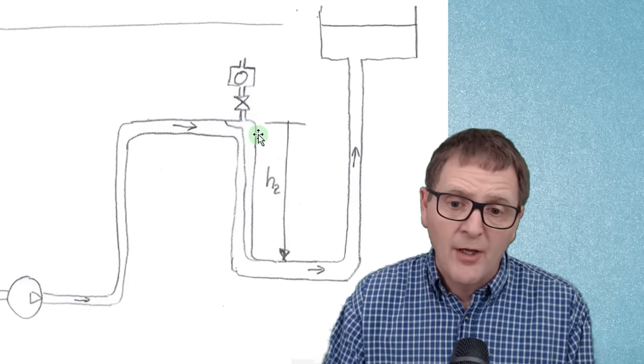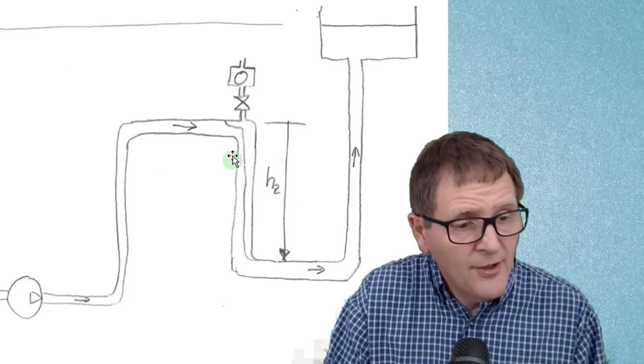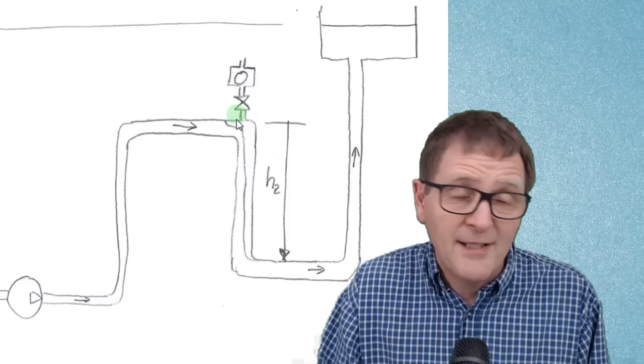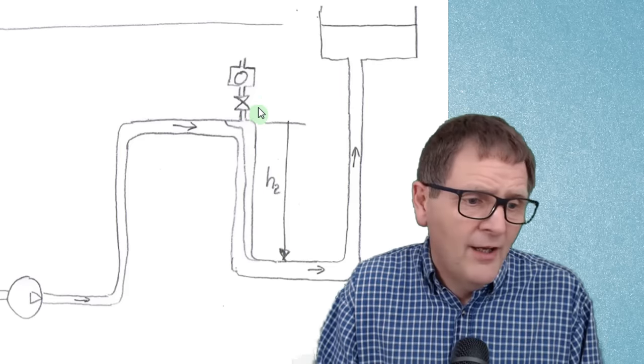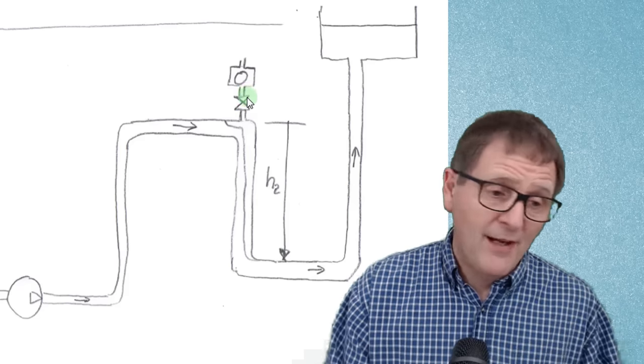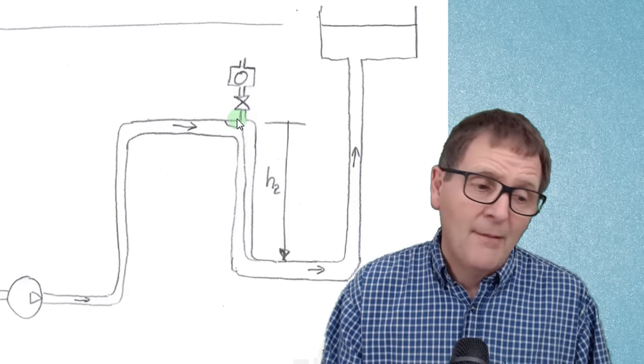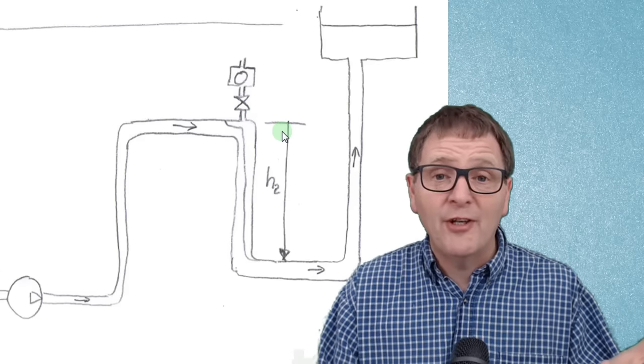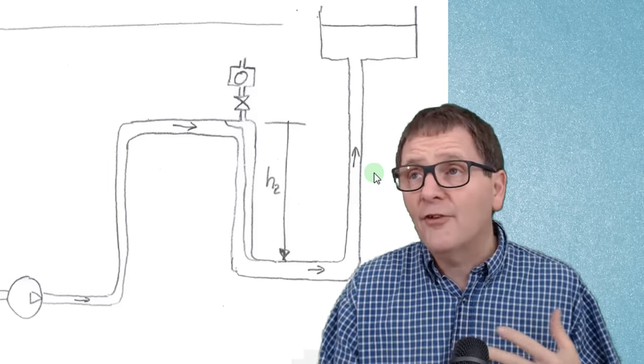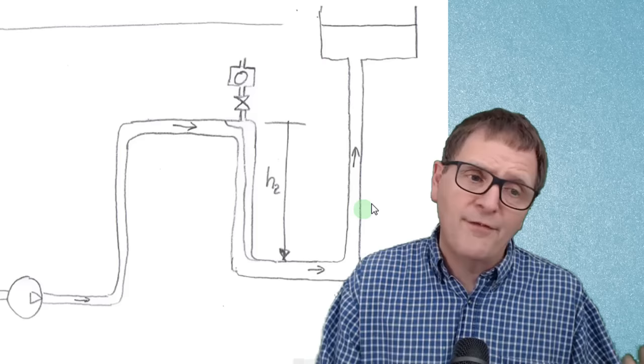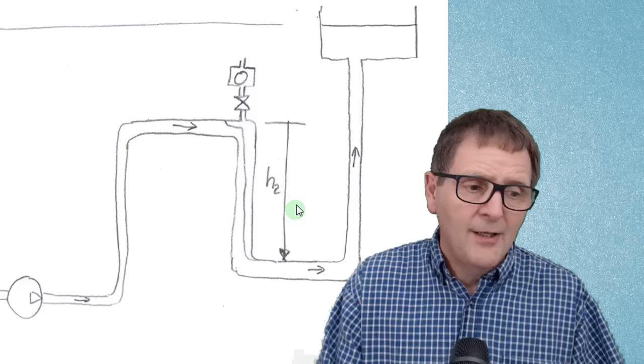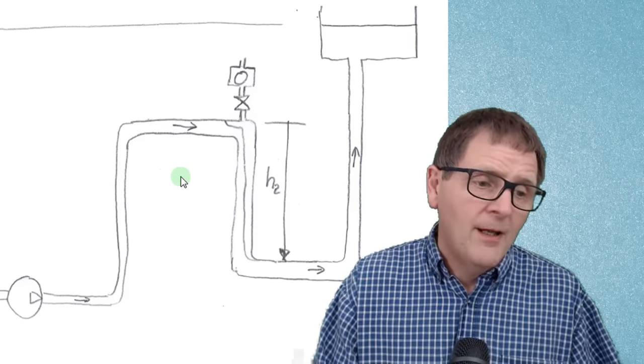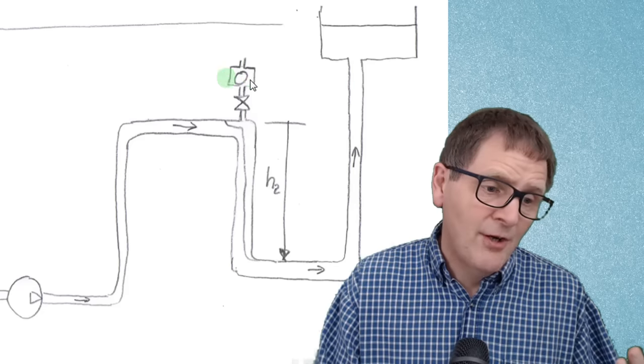What can we do about this air or gas bubble? We could try to design it out, but if we have a gas bubble that we need to control, the only real way is to put a valve at the high point and bleed the gas off. There are two common ways of doing this. The first is a simple isolation valve — you just bleed the gas out manually. This is similar to the sort of thing you might see on a radiator: a bleed valve. These are very useful where you're trying to prime a system for the first time, and once you've got the air out and no more air will be introduced, that works well. But if there's a continual supply of air coming in, a manual valve is not much good.